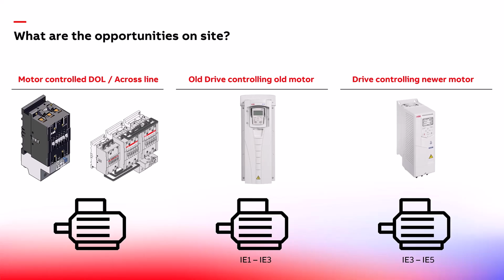I'm going to give some good examples on that. You'll also see drives controlling a new motor as well. So it might be a relatively new motor with a newish drive as well. What I would say, it's always important to look at these as well with your customers and with your end users to see how they're commissioned and see if they're set up correctly.